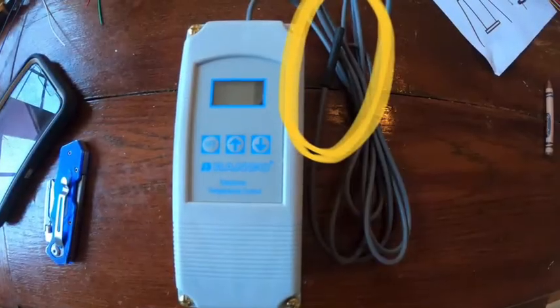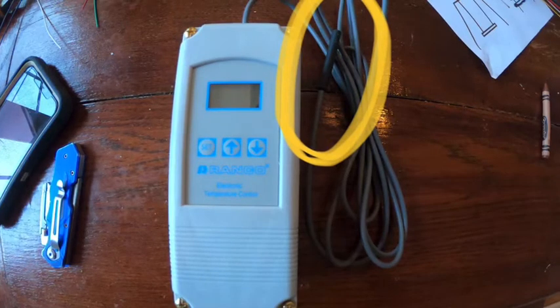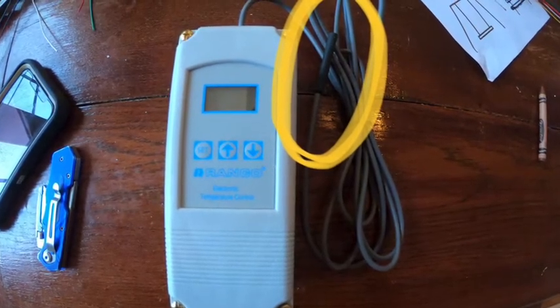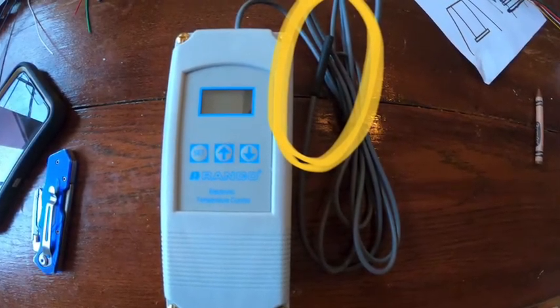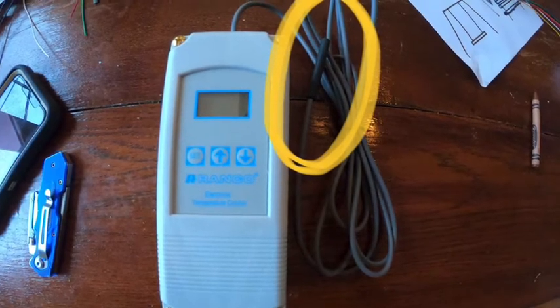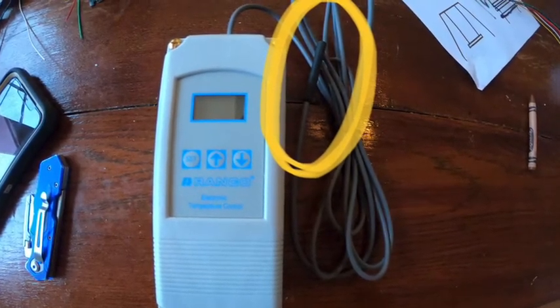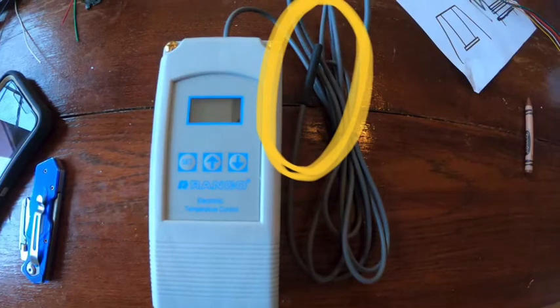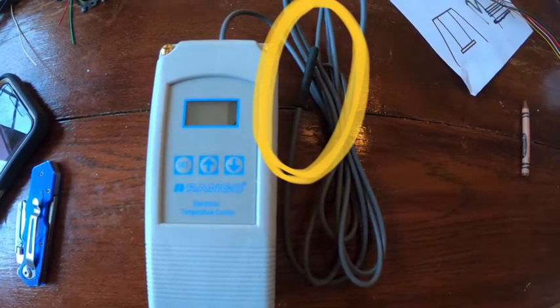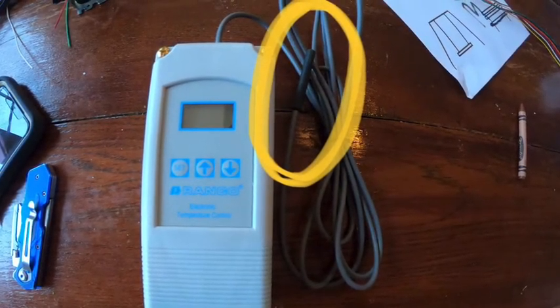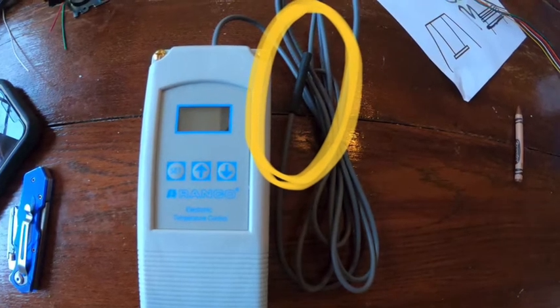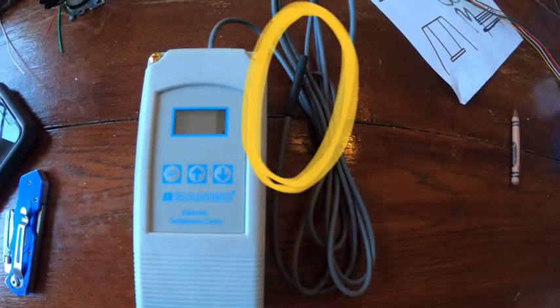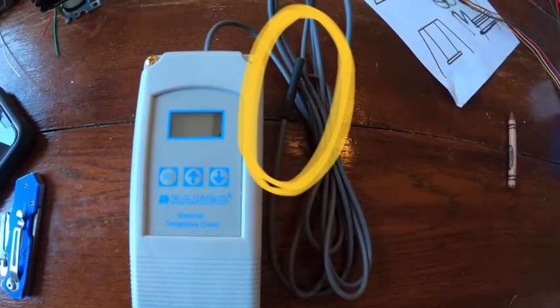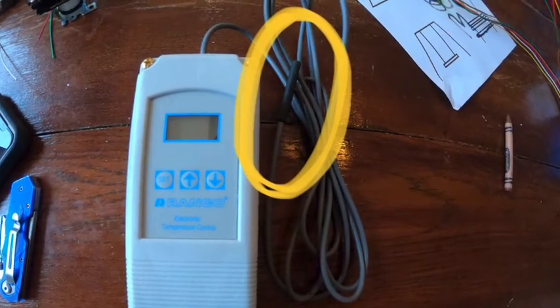Once everything's all wired up, the last thing you'll have to do is connect the probe for your Aquastat to the supply line for your heat exchanger that's already tied into your ductwork. What you'll want to do is make sure it's nice and tight, like a hose clamp, and then wrap it in some nice insulative tape. That way you're getting the most accurate reading to make sure that your heat pump isn't firing when it's not supposed to.